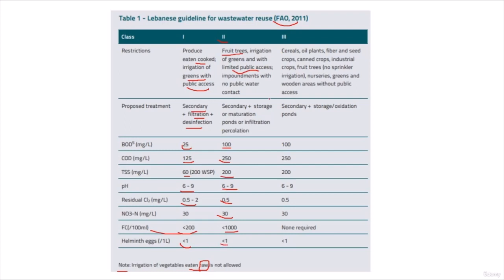Class 3 covers cereals, oil plants, fiber and seed crops, canned crops, industrial crops, fruit trees with no sprinkler irrigation, nurseries, greens, and wooded areas without public access. The proposed treatment is secondary plus storage oxidation ponds. Requirements are similar to Class 2, but fecal coliforms are not required.